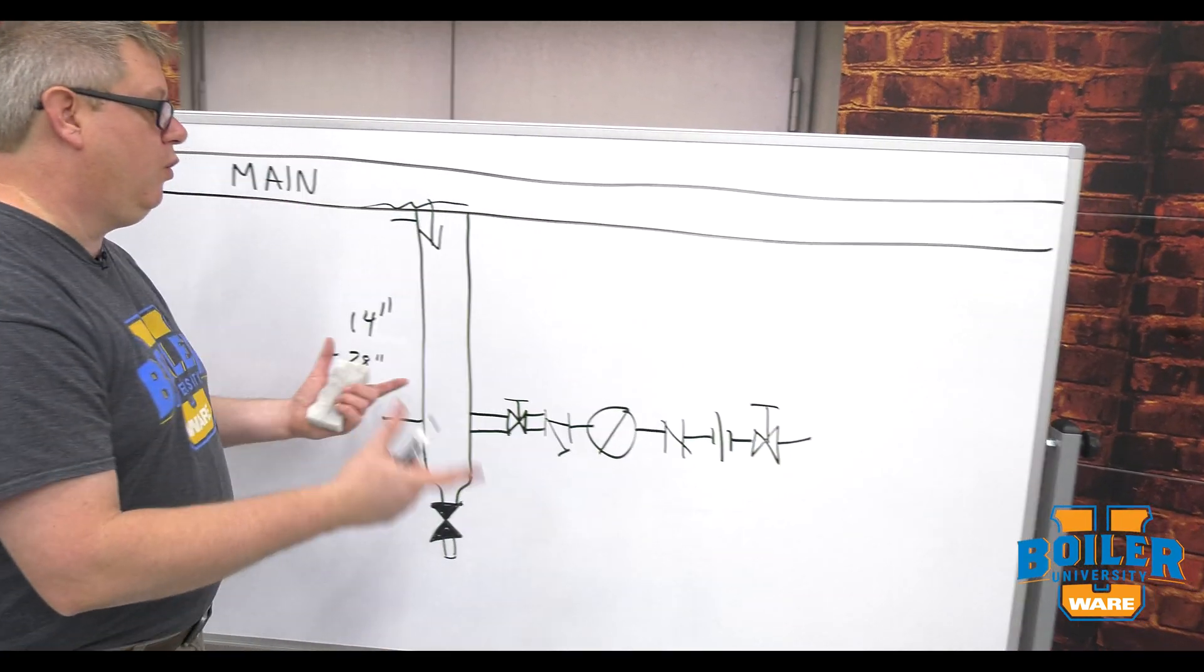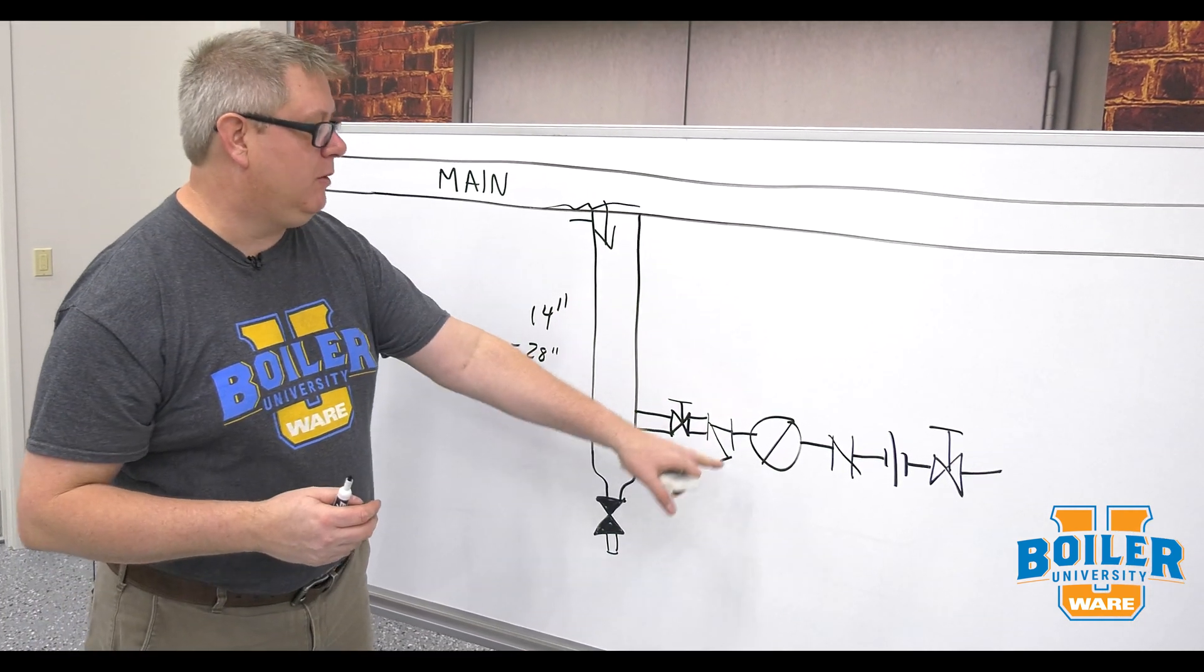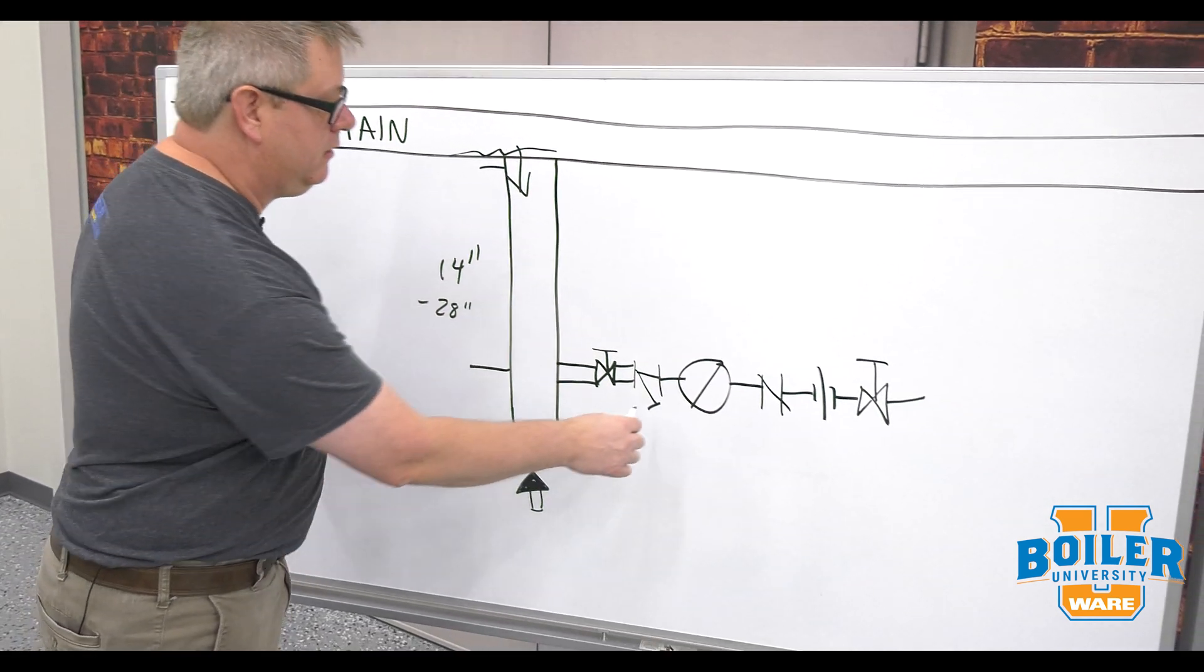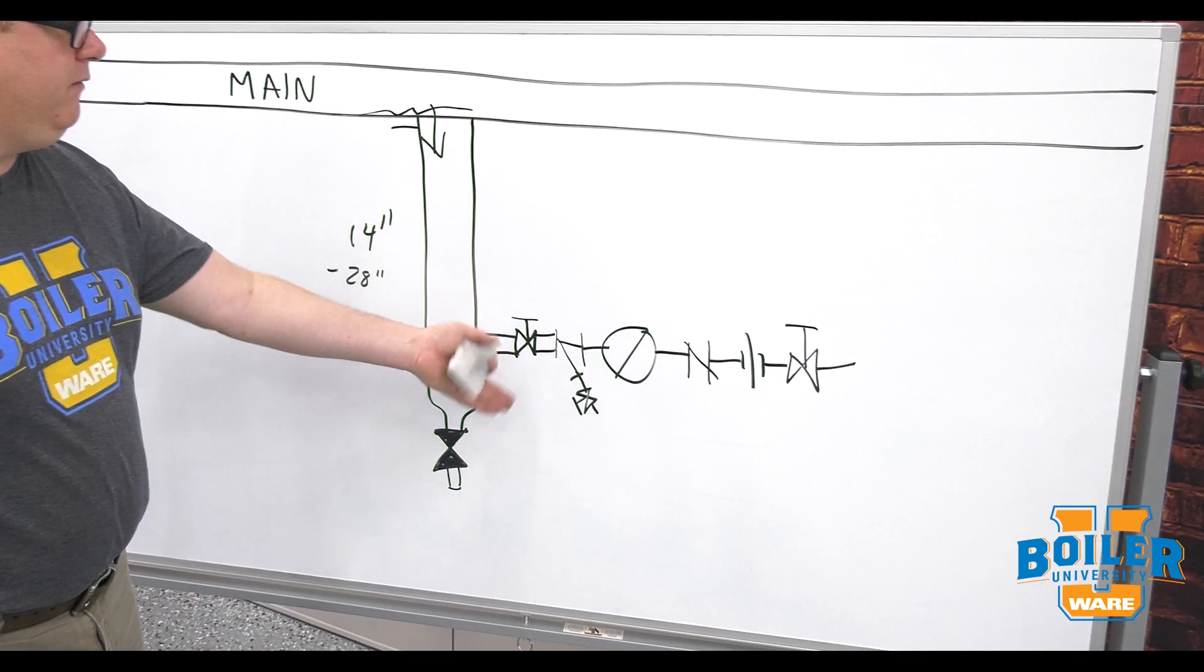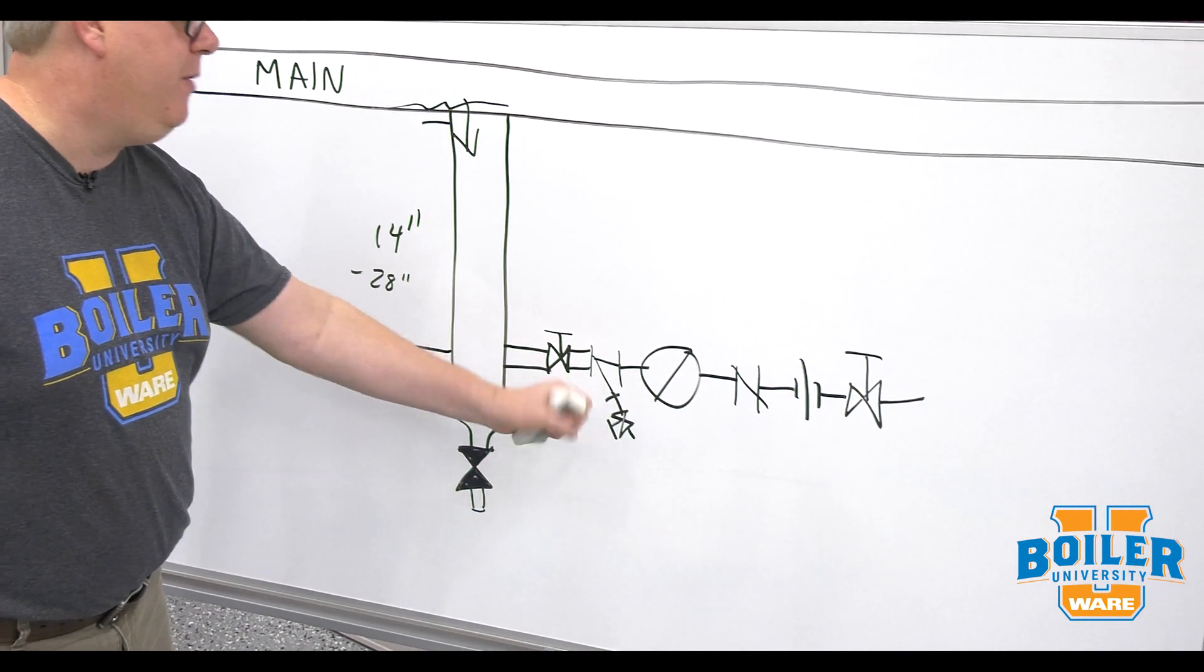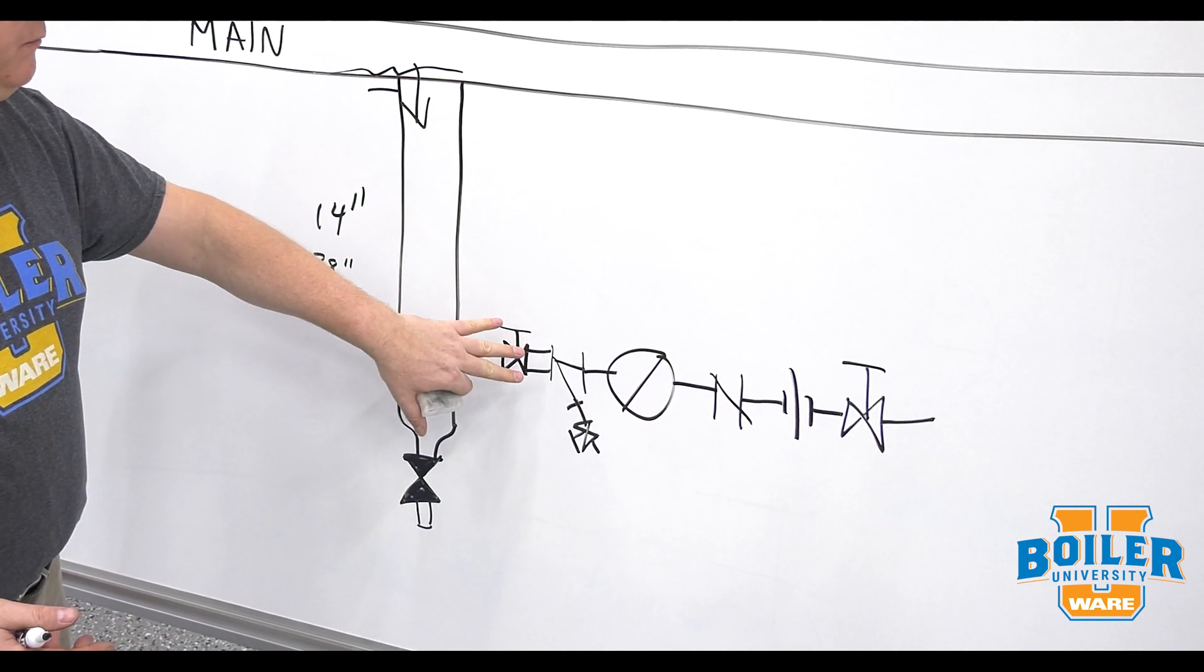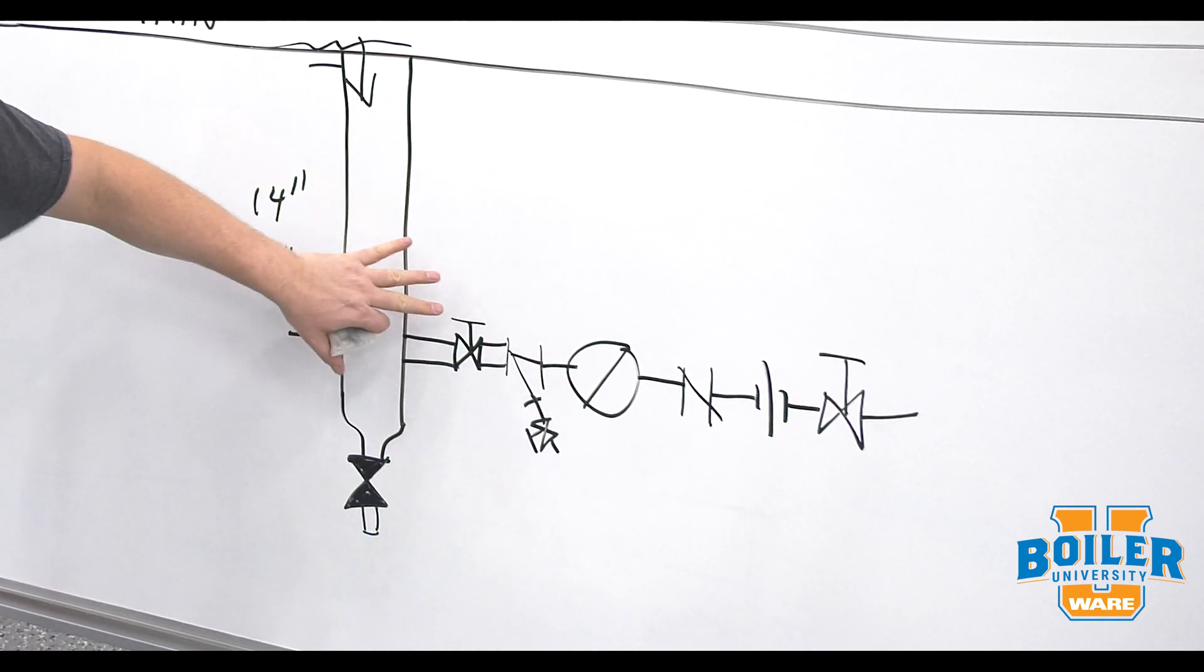Now every plant's got different rules. We may not be able to blow down this strainer trusting that that valve works by removing the plug so it's not a bad idea to put a valve on the outlet of the strainer. That way we can open that valve and not have to worry about this valve holding completely. We can verify that it is if needed.